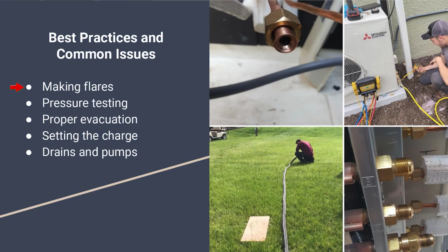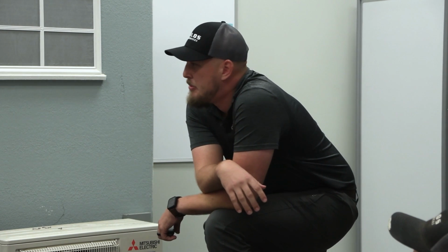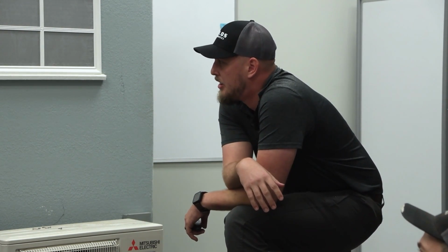So flares are a big one. A common callback is leaks on flare joints. They may look okay, but over time, through vibration and expanding and contracting of copper, leaks do occur. So slowing down and following the correct process for that is important.